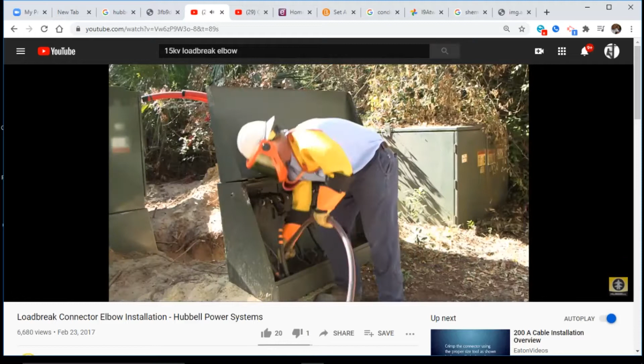Now that's a great example right there, guys. How is he installing the cable in conduit? How's he getting the wire in? Pushing it, yeah. There's a lot of rigidity. That cable is fairly rigid, and when you're using the correct size pipe, which is a 2-inch pipe, it's a great fit to keep that wire rigid, and you're able to push it pretty easy.